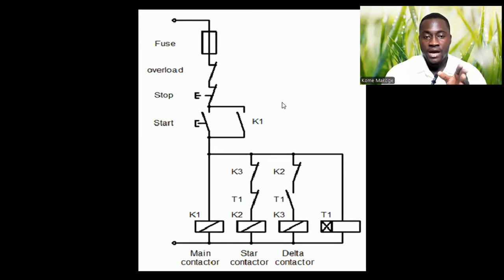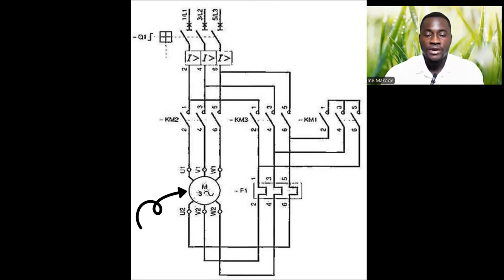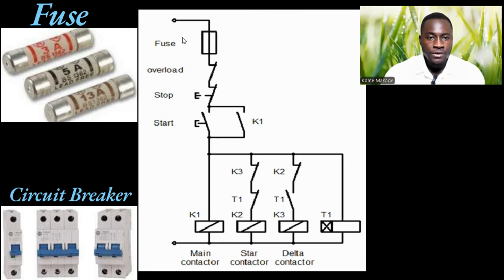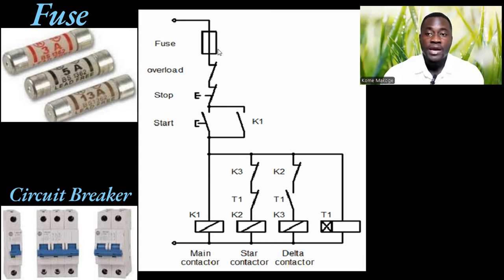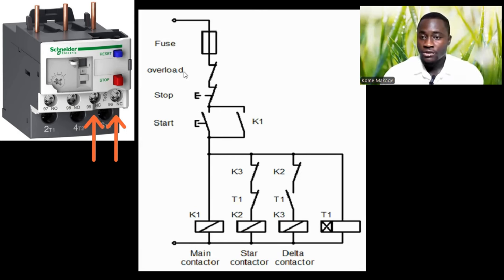We'll be focusing on the control circuit. When you understand how the control circuit functions, it will also help you understand how current is flowing from upstream going to the level of the electric motor and then the motor starts rotating. The first point here is the fuse — or in this case, we can also use a circuit breaker. Any circuit-protective device can be used in this location. Next we have a thermal relay, connecting to the normally closed contact of the thermal relay, which is also an overload protection relay.